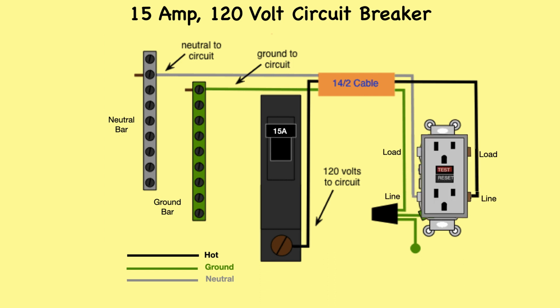This illustrates installing a 15 amp circuit breaker for a 15 amp branch circuit to a ground fault interruptible receptacle, or GFI. The 14-2 AWG cable for this circuit includes 2 conductors and 1 ground wire. This type of receptacle is usually found in bathrooms and outside wall receptacles. Notice that the black hot wire and neutral are connected to the line screws of the GFI receptacle. Additional receptacles may be connected to the load screws of the GFI, making them ground fault protected by this GFI.